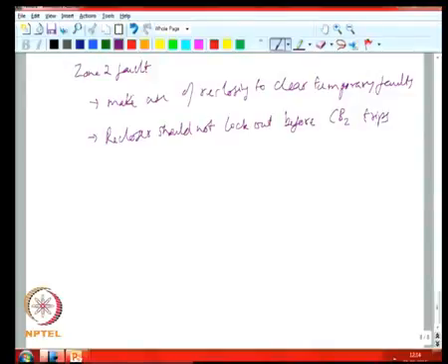So, we will look at what happens in this particular situation when you have fault current at the maximum and minimum of that particular range in this example. Okay.